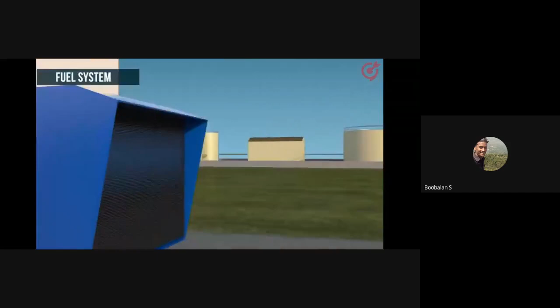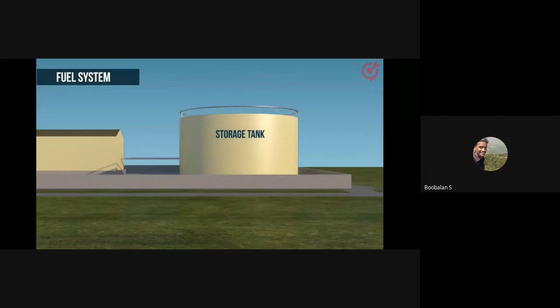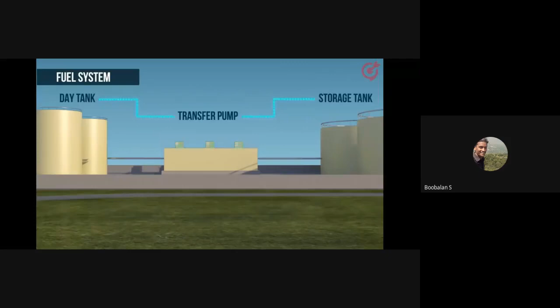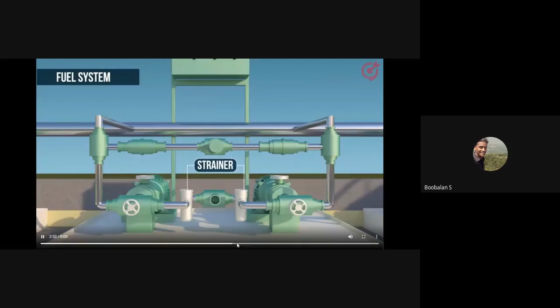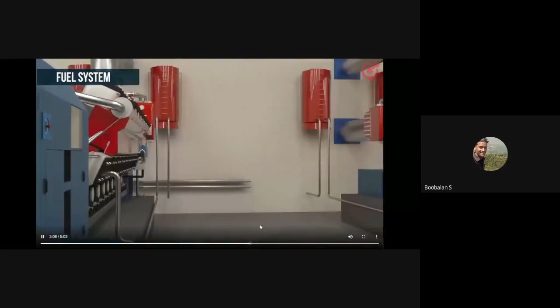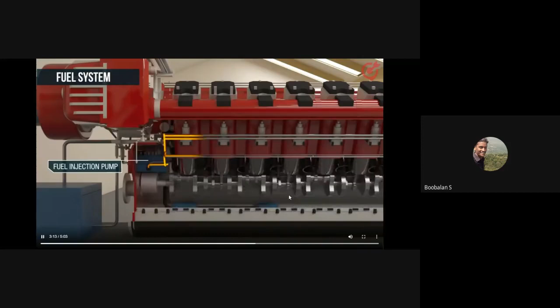The fuel system consists of a storage or main tank to store fuel. Oil is pumped into the day tank via a transfer pump, transferring from the main tank to the day tank. The fuel injection pump injects fuel from the day tank into the engine cylinder at high pressure, about 100 bars.